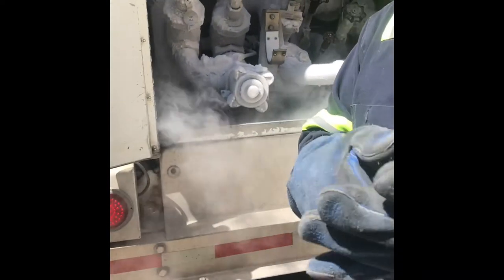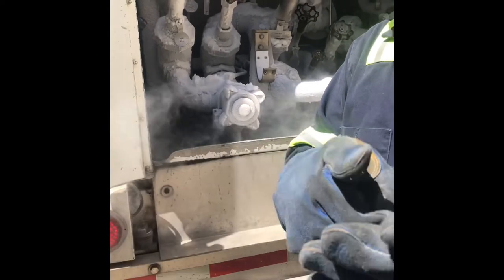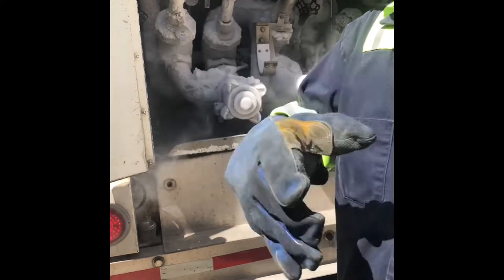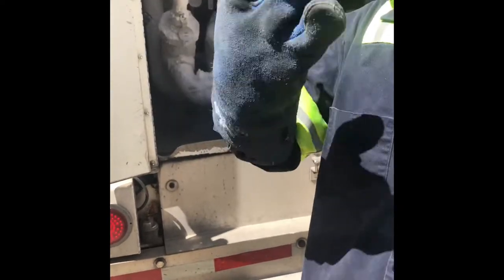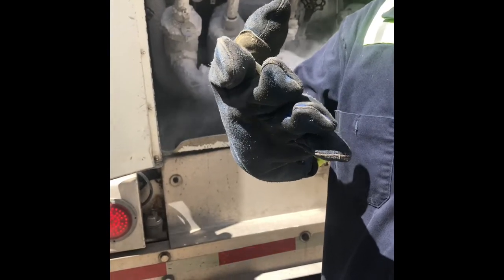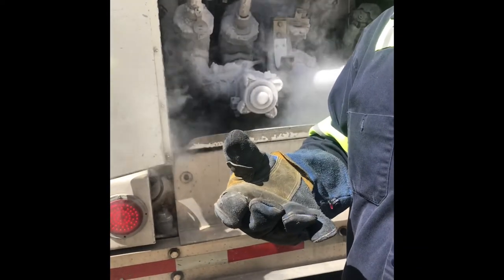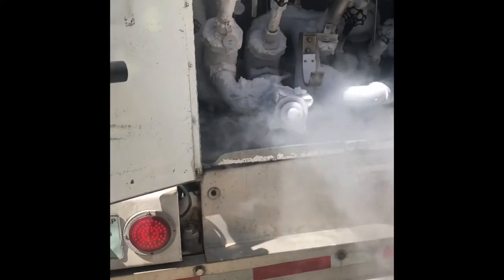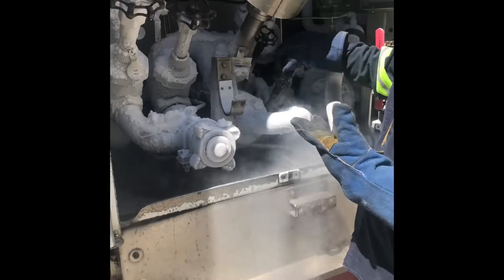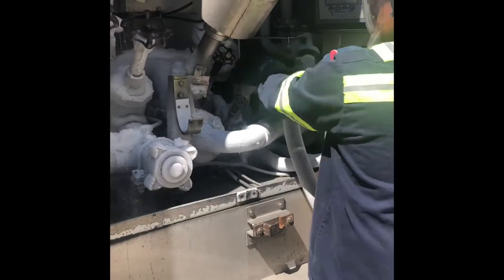The longer that recirculator is open, the faster you lose prime. So the key is to open up the pressure builder three or four turns, so that as you're doing that, your pressure is trying to build rather than lose prime or lose your pressure. So I like to start by opening up my pressure builder. Joystick.